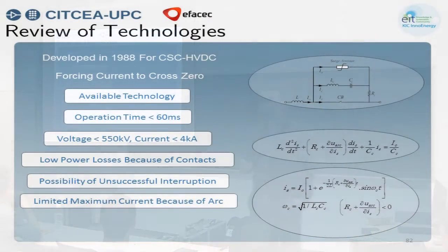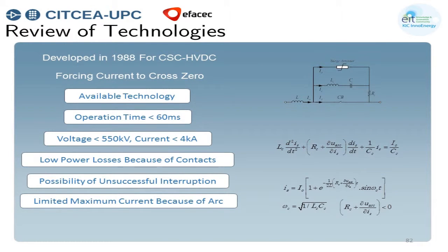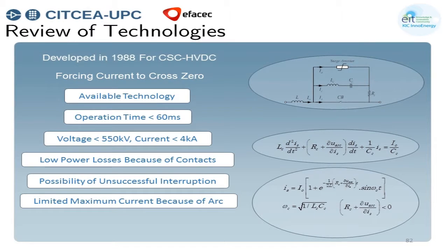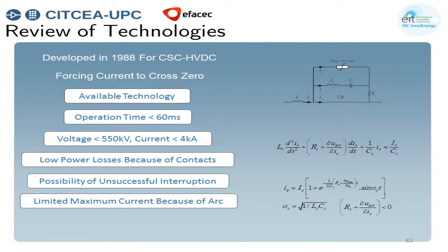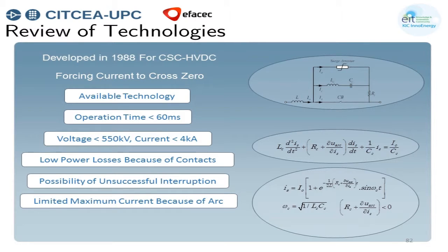Mechanical circuit breakers for HVDC technology are not a new thing. We have had them since 1988, developed mainly for CSC HVDC or thyristor-based technologies. But we know they have not been used there because all the connections were point-to-point, so it was possible to interrupt the fault currents from the AC side, and CSC technology, unlike VSC, is not so vulnerable to DC faults. This technology has an operation time of less than 60 milliseconds.